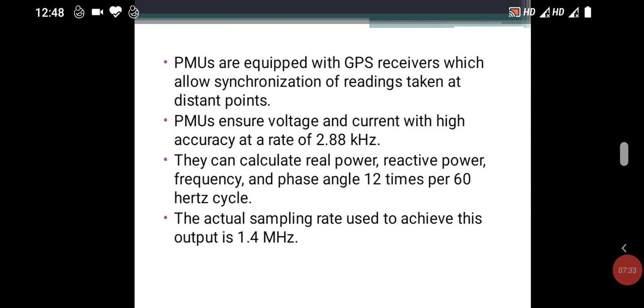So they can calculate the real power, reactive power, frequency, and phase angle around 12 times per 60 hertz cycle, 12 times, because this is the difference between the SCADA and PMU. The speed of capturing the data is very high compared to the SCADA. So the actual sampling rate used to achieve this output is around 1.4 million hertz. So it is a very high frequency device.